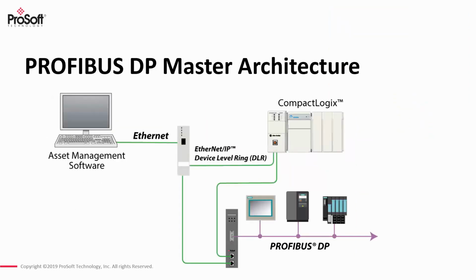When we look at a typical PROFIBUS DP architecture, a master device is the one that is controlling the PROFIBUS bus. Devices such as HMIs, drives, and even distributed I/O blocks will be sitting on a master, or our module would need to be a master talking to those various devices on the network.